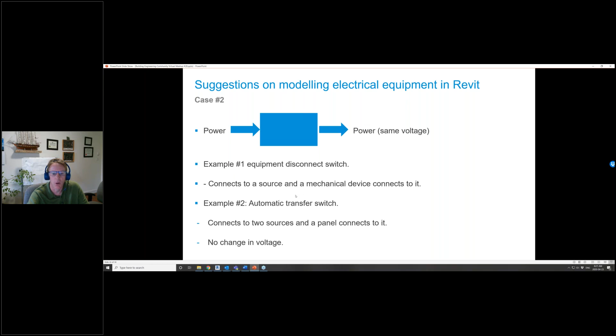Number two: you saw in the one-line diagram we showed an automatic transfer switch. We model these as well as panels, since Revit gives you the ability to set up multiple sources on a panel. That's how we handle a transfer switch. And with a transfer switch there's no change in voltage, so the panel class works well.